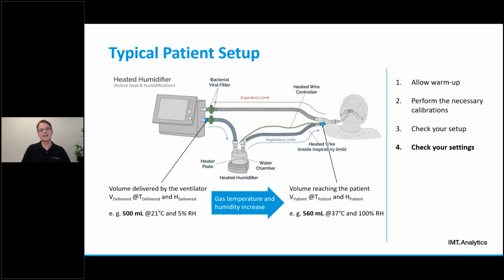What ventilator manufacturers usually do is that they compensate for that with their setting and monitoring on the device, as they can all calculate this through gas standard conversions. So in our example, the setting and monitoring value on your ventilator you would typically see in this situation is not the 500 ml delivered to the circuit system, but the 560 milliliters that ends up being delivered to the patient. Okay, so they compensate for that. As 37 degrees C is also the typical body temperature, the gas condition at this temperature and 100% humidified is called BTPS gas standard, which stands for body temperature and pressure saturated.